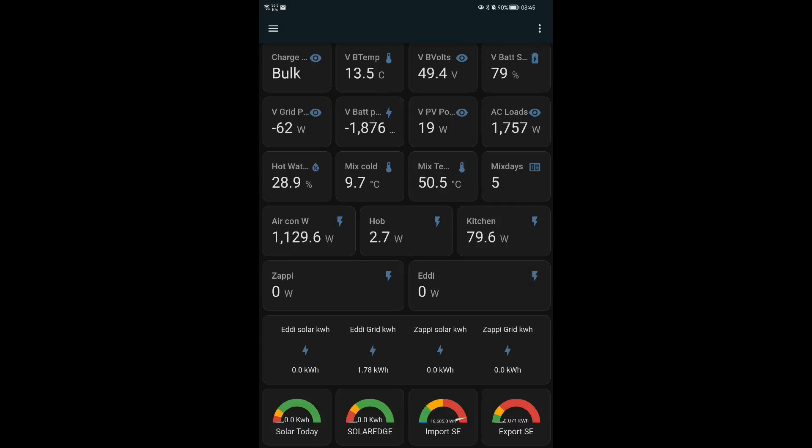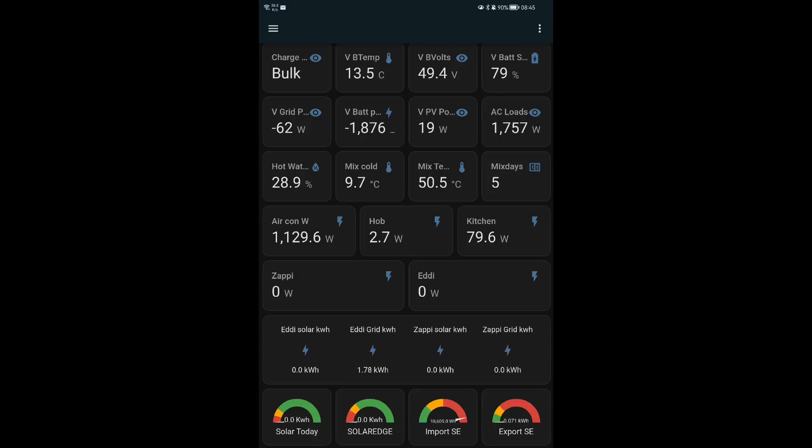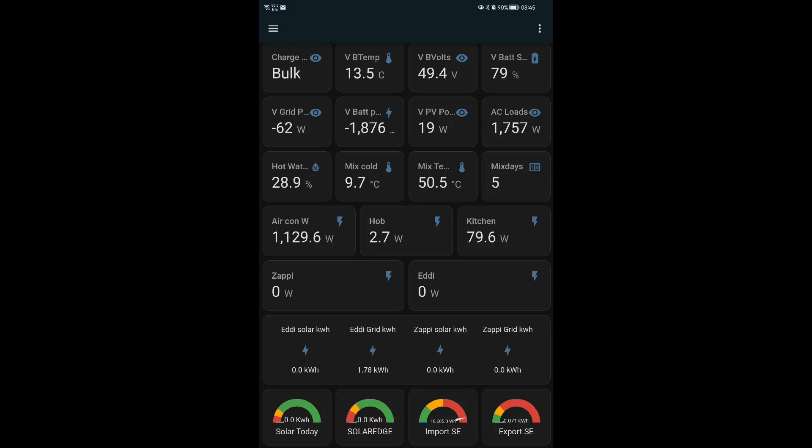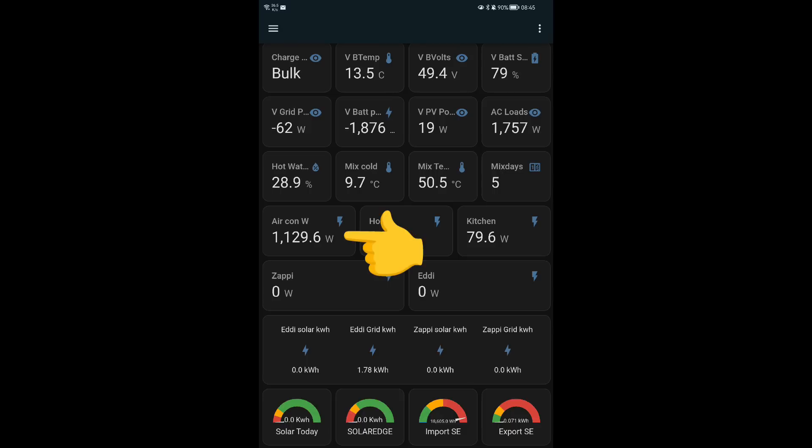So this is where it all started the other day, 8:45 in the morning. I was checking the system, having a look to see what battery we've got, and on my Home Assistant view, showing all sorts of data from my Victron inverter, from the SolarEdge inverter, from MyEnergy. It's data coming from everywhere, all accumulated in one place under Home Assistant. So I was seeing my battery has 79% charged. But it would have been fully charged at 5:30 in the morning from charging overnight. So I've already used 21% by 8:45 in the morning. So that's heating. The battery is currently discharging 1.876 kilowatts. The AC load is 1.757 kilowatts. The air conditioning heating is actually consuming at the moment, 1.129 kilowatts. Lots of heating because it's cold and that's drawing the battery down low.